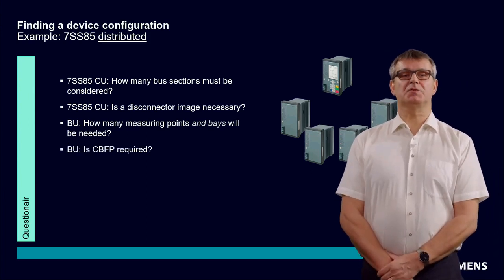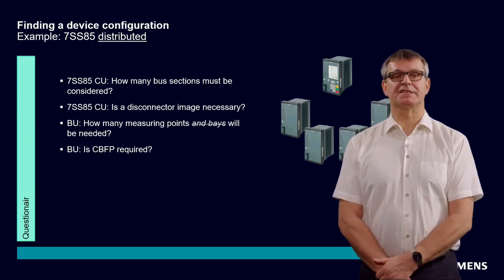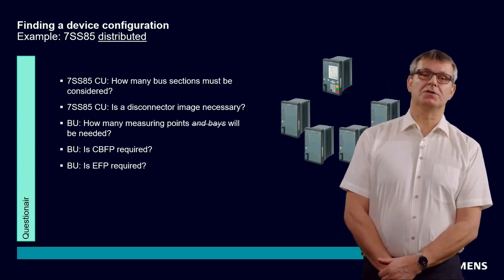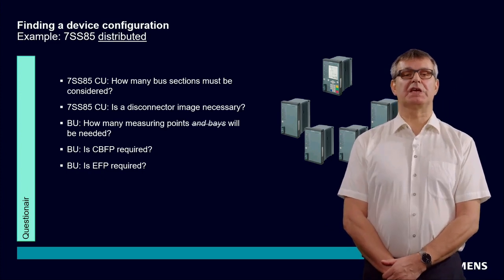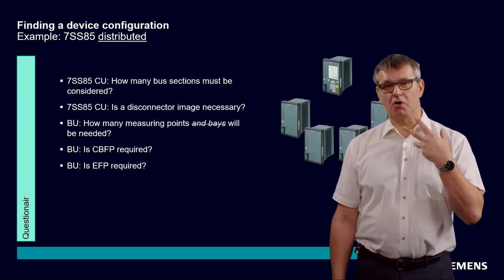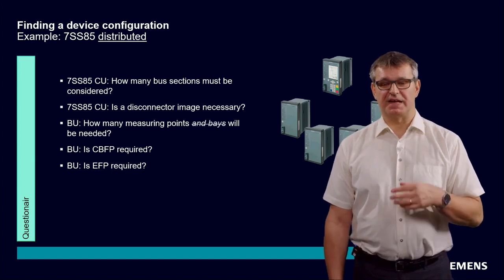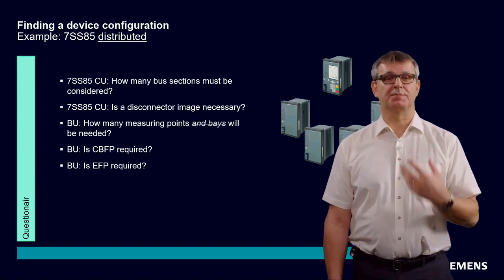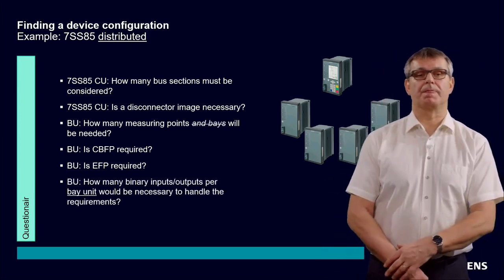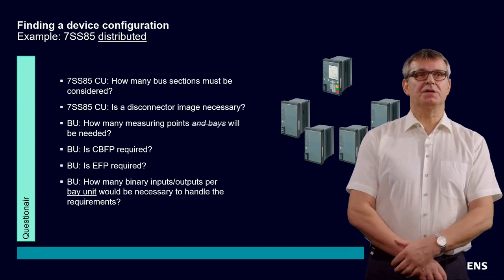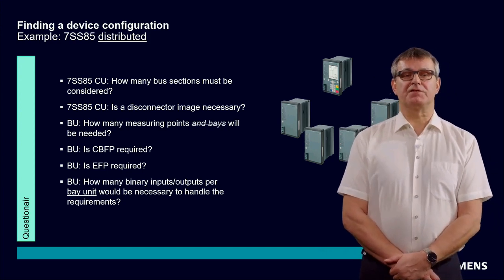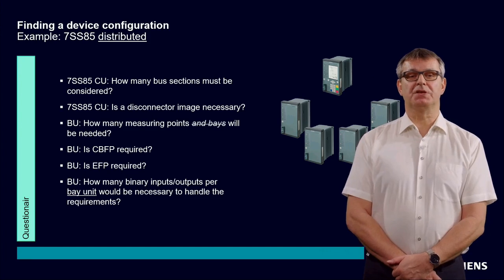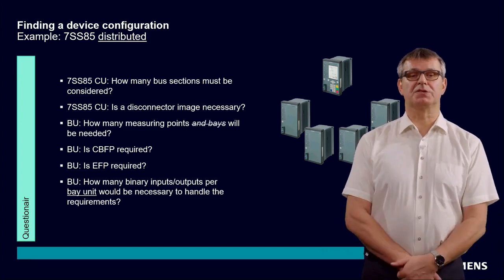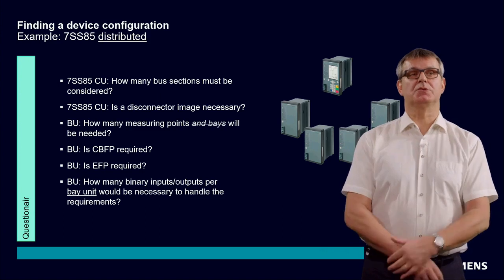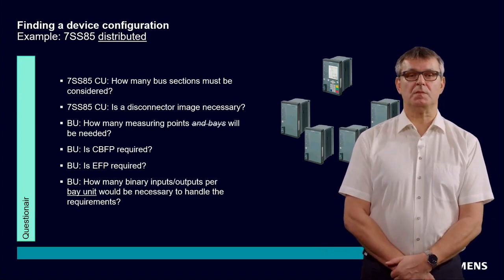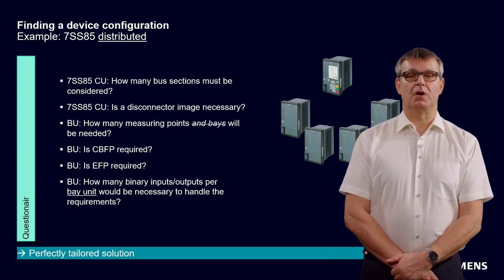Do we need circuit breaker failure protection? This question is also necessary for the bay unit. And the end fault protection must also be located in the bay unit. So all in all, backup protection functionality must be located in the merging unit, in the bay unit. And of course, for the bay units it must also be answered how many binary inputs and how many outputs I need in the bay unit. Okay.